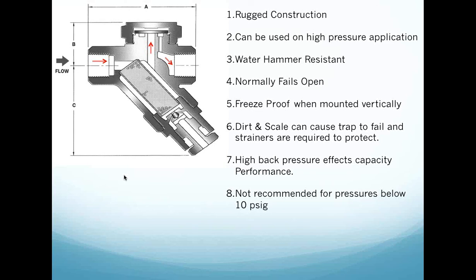Be careful about oversizing these things. I will tell you that if you have air in the system, this trap is okay for air handling, but what I do on this particular trap technology is turn it into a horizontal position, with that strainer on the built-in body of this disc trap, and that helps me to process air and non-condensables better. Okay, normally fails open, hammer resistant. They're freeze-proof when mounted vertically. Dirt and scale can cause the trap to fail. That's why we have to protect them with strainers.